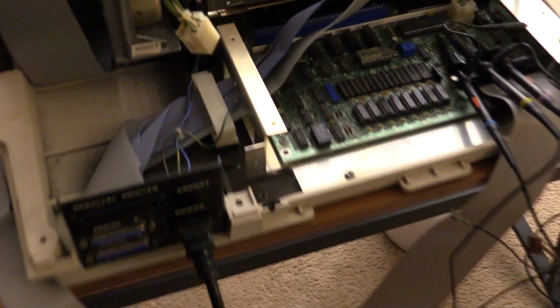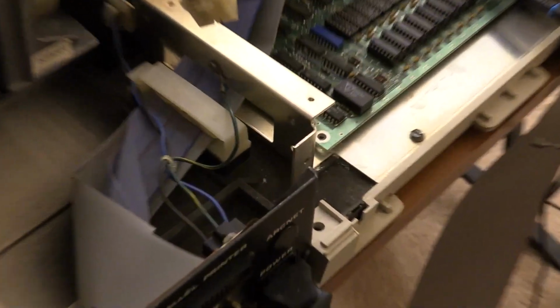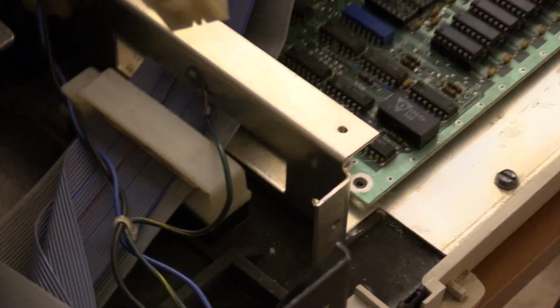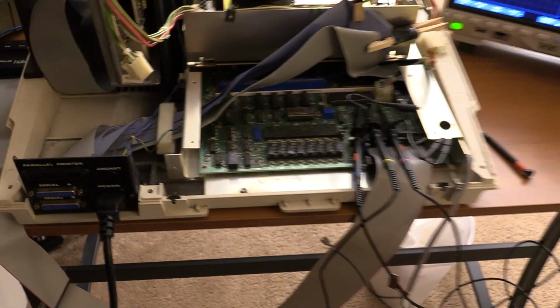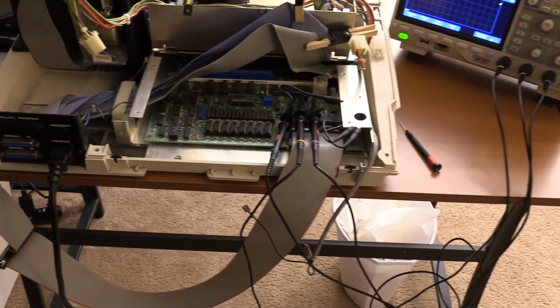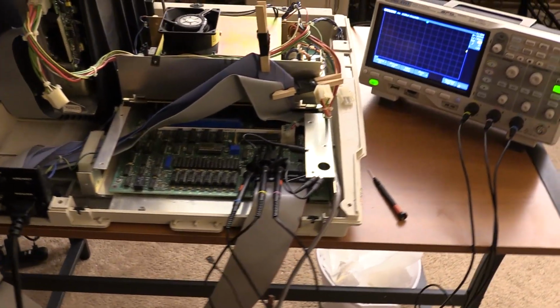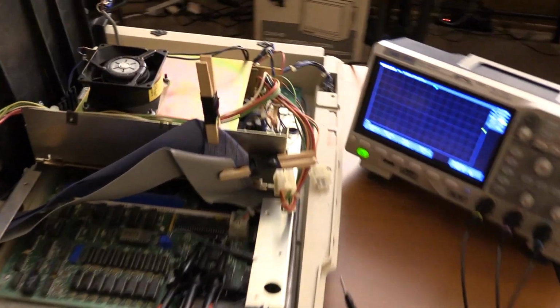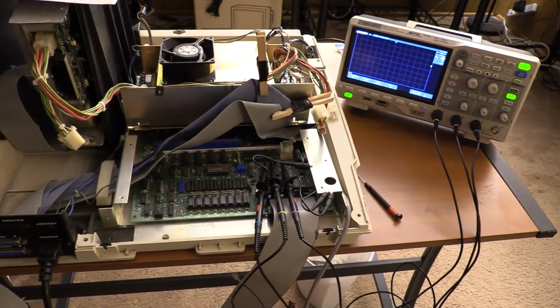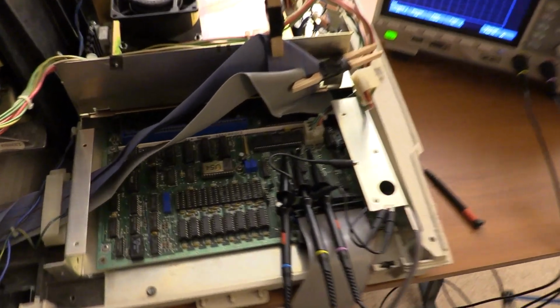Okay. And one other note, when you unplug this, or when you take the card cage off, you have to take off the grounding wire. Make sure you put it back on. I happened to catch it as I was getting ready to plug the machine in, otherwise I wouldn't have had a ground reference, and that would be dangerous for me too, because the machine wouldn't be grounded. So, if the frequencies all come out right, or if I can't get them right, one of the things we will possibly do is take a look at this floppy controller.